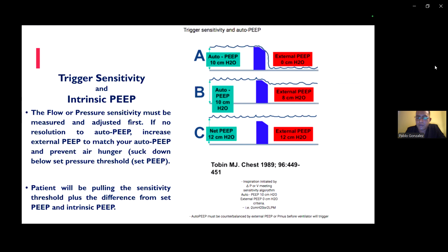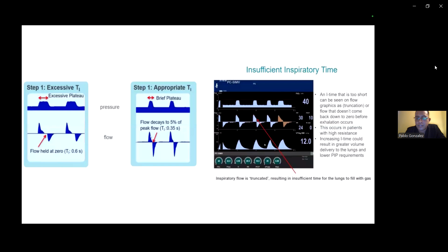Here's an example of I time, when it's excessive and when it's appropriate. On the left side, you have an excessive plateau here, and there is flow held at 0 with a 0.6. And in this example, you have an appropriate plateau with an appropriate I time of 0.35. And as we go into the right side here, it's an insufficient flow and I time to fill in the lungs. So I've seen this multiple times.